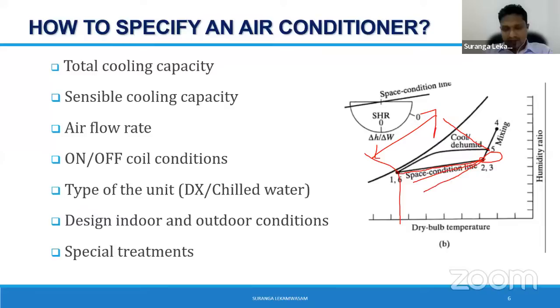If your latent heat component is high, probably the slope of the line becomes bigger. Sometimes it comes to a level where it doesn't touch the saturation line, the 100% line. That's why you need to think of reheating to bring this point to touch the room line. So all these psychrometric processes you need to understand thoroughly, but very easily you can find all these figures with the psychrometric process.